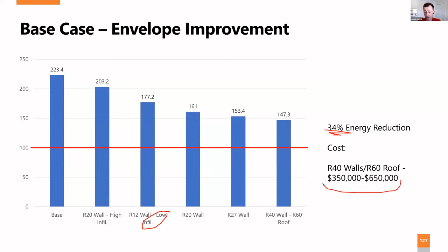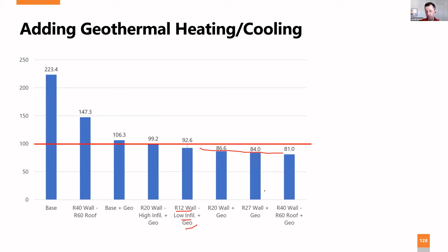So let's take that, call it the passive scenario, and compare it to geo. So this is the base system with zero upgrades except ground source heat pumps. We can get down to 106. It's a 52% energy reduction. If we do R20 walls with high infiltration, we get to net zero, but we're better off leaving it at R12 walls with low infiltration and adding geo. And you can see that as you improve the building envelope, the geo energy usage drops very minimally, again, because we flatten that curve. And envelope upgrades don't really make much sense.